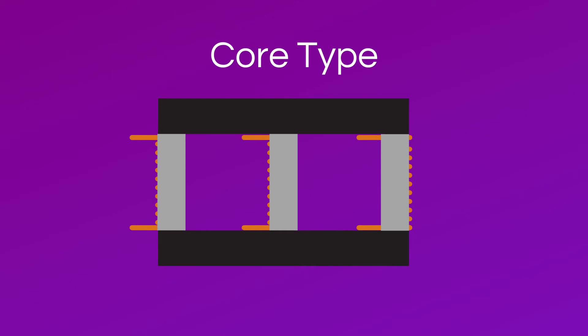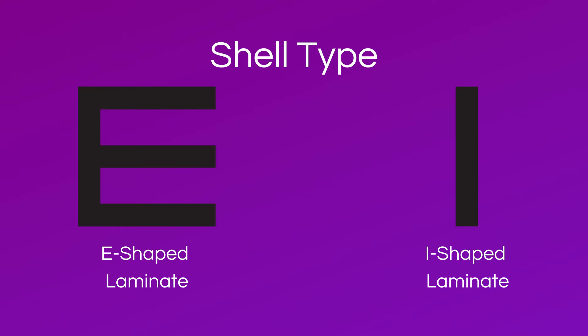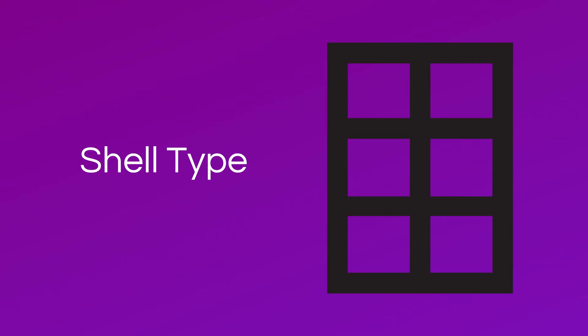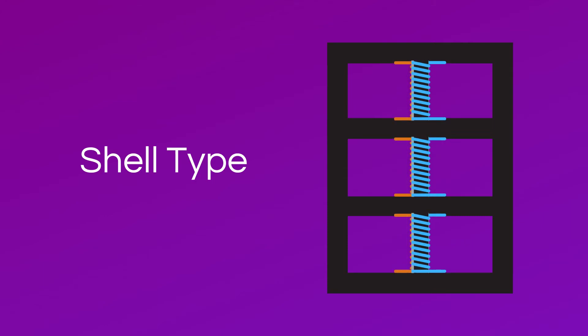Now onto shell type transformer cores. The single phase shell type is constructed in the exact same way as a three phase core type transformer, as it also uses E and I laminates. However, the primary coil is only wound around the center limb. Then, like the three phase core type transformer, an insulator is wrapped around the primary coil and the secondary coil is wound around the insulator. A three phase shell type transformer core is a rectangle with six empty squares inside, creating three limbs that the primary and secondary coils wrap around. The windings operate similarly: the primary coil wraps around the limb, then an insulator wraps around the coil, and then the other coil wraps around the insulation.